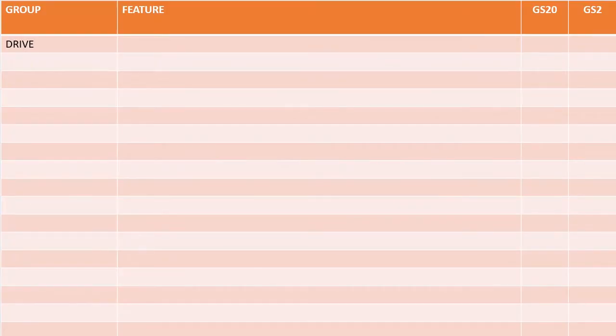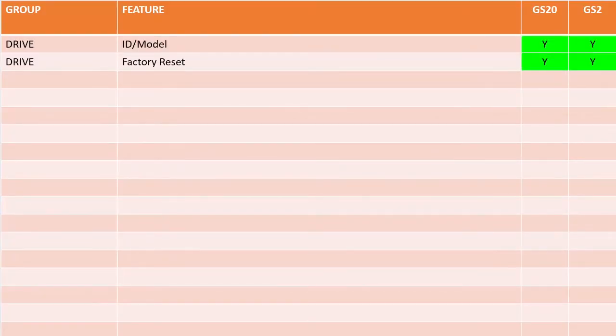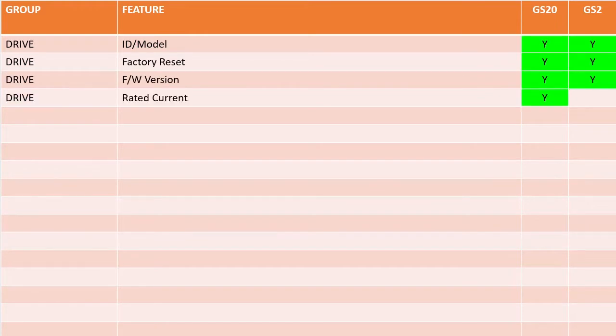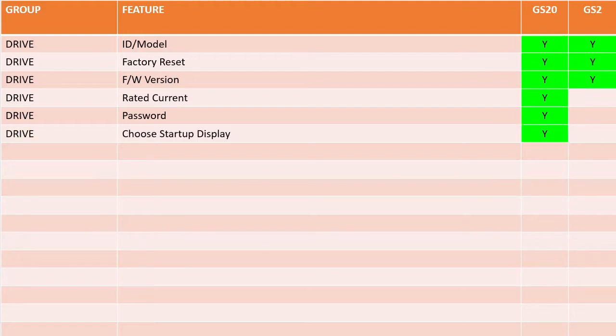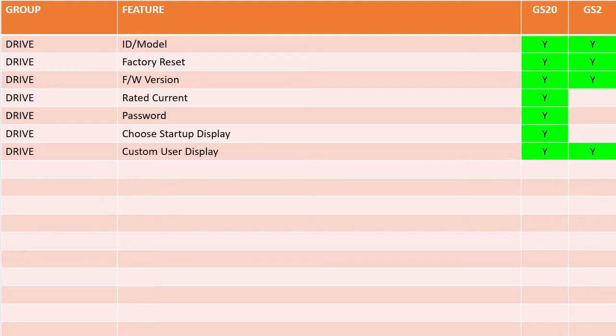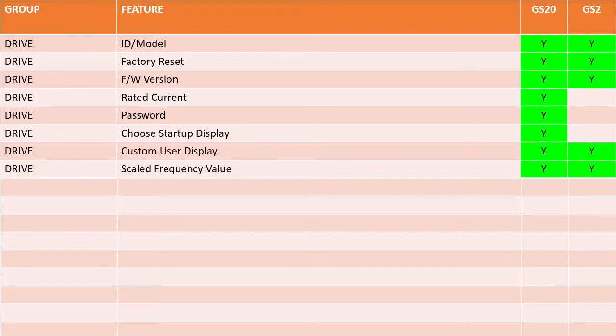The drive parameter group covers the usual drive information, but the GS20 also provides the rated current, the ability to password protect your parameters, and you can tell it what you want it to display on powerup. I love having the rated current handy, especially when trying to debug over-current issues — I don't have to go digging through spec sheets to find that number. Both families have a custom user display and the ability to scale the frequency for display.